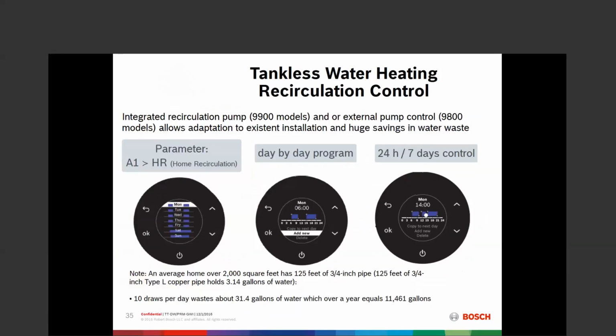And when we say manage it, it is actually a scheduler by day of week. We can schedule by day of week, time of the day that we want the domestic recirculation on, and time of the day when we don't need domestic recirculation. So the behavior for the unit is this. We have this period set up here for recirculation that's going to start at 6 in the morning and end at 9:30 in the morning.